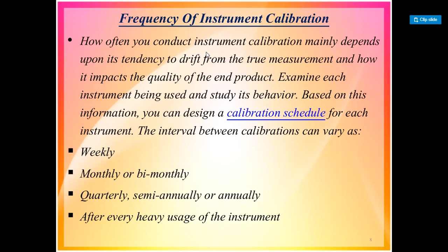If any equipment is being used several times, then the frequency depends on the equipment. If any equipment undergoes a heavy weight or heavy load, then we have to calibrate it after every weighing. Or if the equipment is, for example, a weighing balance, and we are using it rarely or continuously, we will calibrate it weekly. This frequency is also completely dependent on the vendor or manufacturer's recommendations.